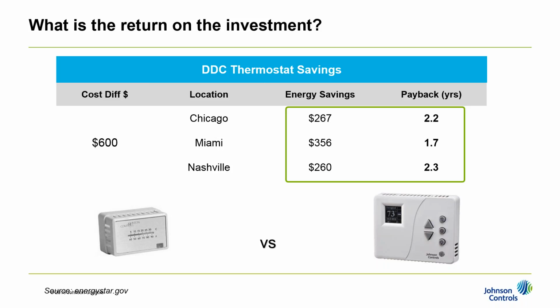Could someone wire the occupancy contact as a simple mode control without a front end using relays? As long as a dry contact signal is given to the WT4000, it will interpret open as unoccupied and closed as occupied. So whatever that implementation happens to be, we can feed it in that way.